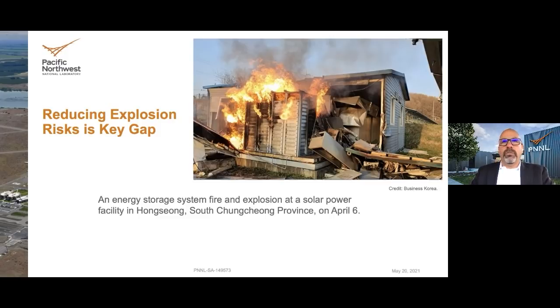The clean agents are very effective at visible flame, but they're not shown to be effective at deep-seated thermal runaway fires. So we've seen thermal runaway that produces a lot of flammable gases with no fire to put out, and those gases continue to be produced. So we really feel that the explosion risk is the greatest risk.